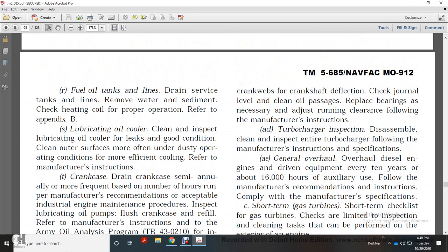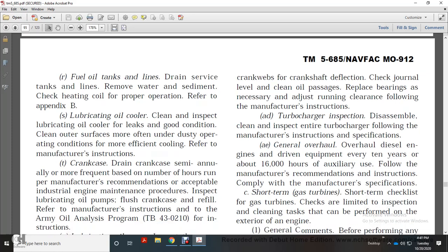Fuel oil tank and line: drain and strip the tank and line, removing water sediment, and check the heating coil for proper operation per appendix B. Lubricating oil cooler: clean and inspect the lubricating oil cooler, keeping the outer surface clean and free of dusty operating conditions for the most efficient cooling, per the manufacturer's instructions.